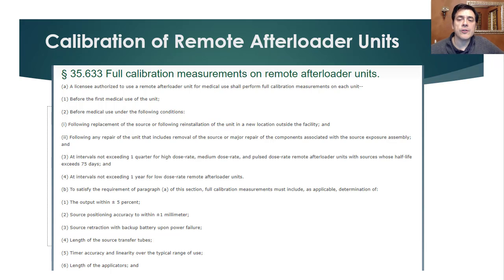35.633, the full calibration measurements on remote afterloader units. It essentially says that every time you replace the source or every quarter, you need to do a full calibration. So the potential sticking point for this, and this is with sources whose half-life exceeds 75 days, is if you're not doing 4 source exchanges a year, you have to add a full calibration if it happens to be less than 4 source exchanges per year.